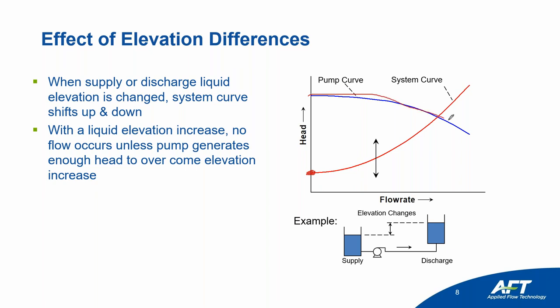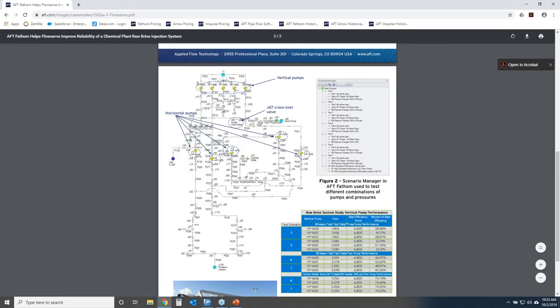Now, this particular pump that we're using generates a lot more head at zero flow, so it will work for your system. But there are some unique aspects of this for the case of if you're trying to prime a system or not. If you're trying to prime a system, there might be some siphon effects and intermediate high points. If your pump curve looks like this, but the actual pump needs to overcome any amount of head for an intermediate high point, maybe you need a little bit more in that case. Now, I'm not going to go into a lot of detail about that, but let me show you what I'm talking about. Let's see, make sure that all of you can see this.